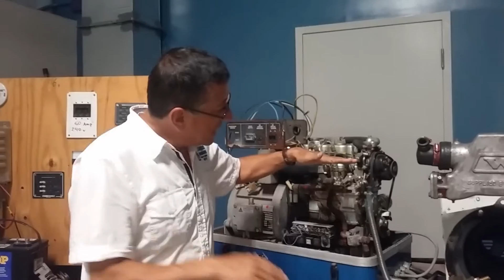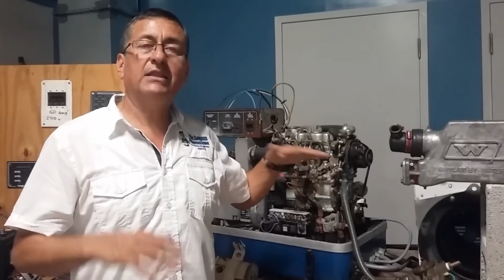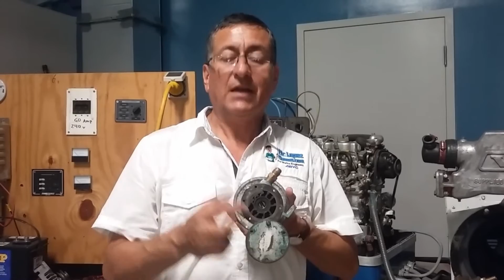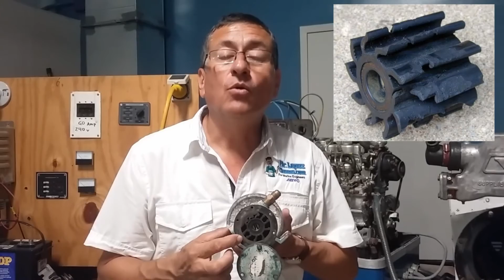When the engine is located below the water line, you are 100% sure that this raw water pump has water all the time. And the impeller, internally, will be protected. Remember, the enemy of the impellers in the raw water pump is the air. When the engine starts and the raw water pump doesn't have water here, the pump suctions air. Immediately, when the impeller is spinning, the air expands and burns the impeller. This is a critical situation. When the impeller is burned, it's like the picture that you have in the corner right now on your screen. The blades are gone. Be careful with that.